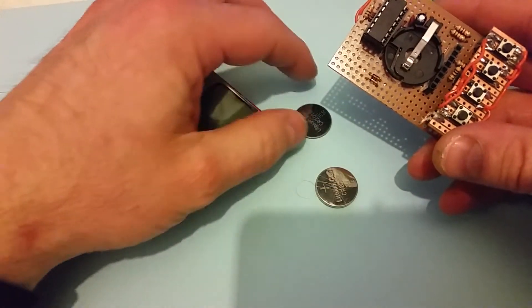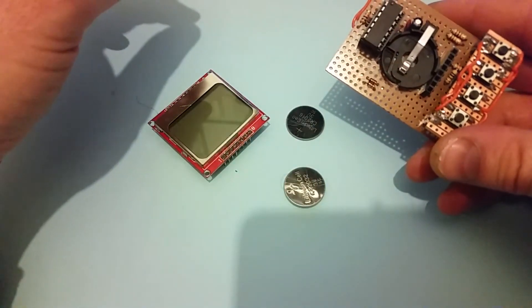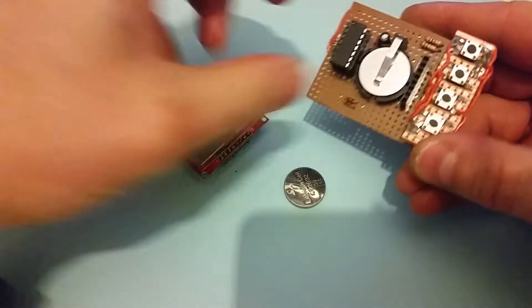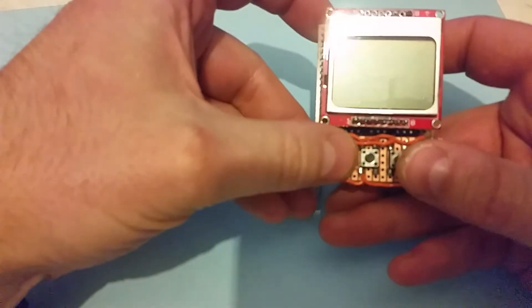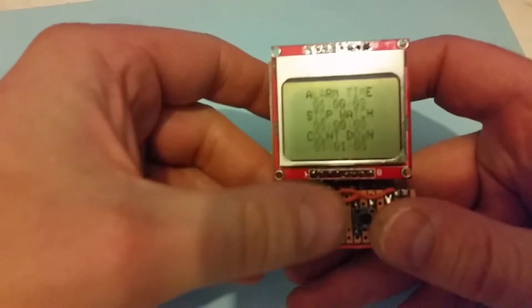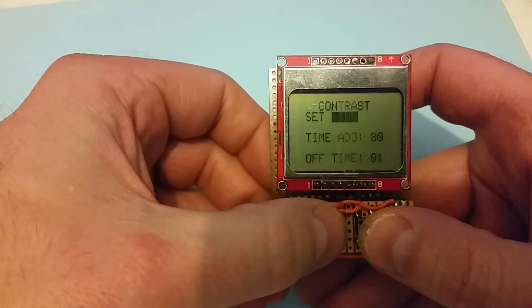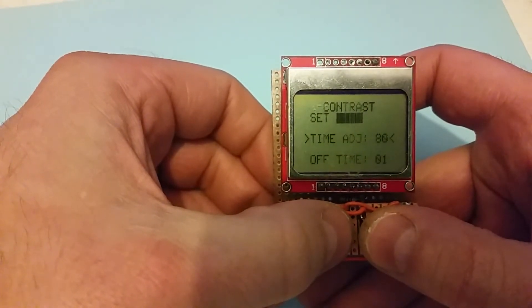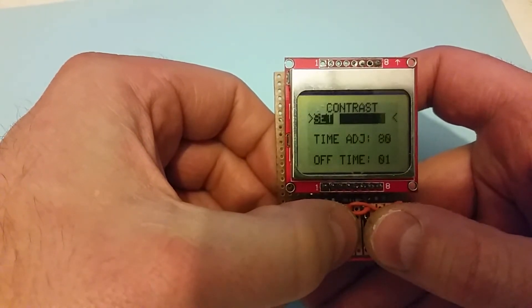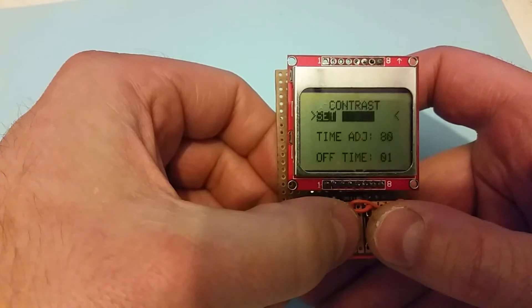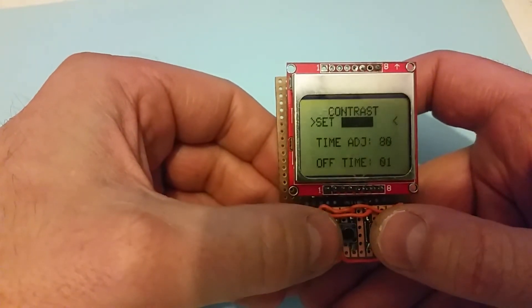So finally I am going to go back to the first device again. And I have got two batteries here. So one has sort of used its charge a bit, that one, and this one is brand new. And I will show you the difference on the first display where you set the contrast, the difference between the contrasts. So I will put the first battery in and wake the device up. And if I go across and bring it into display a bit better and go into contrast, so you see you can boost the contrast on this one. And so this is this slightly discharged battery, and the characters all look okay and everything, and there is no issues, and they are very evenly set the characters.